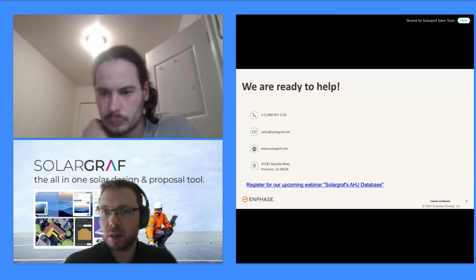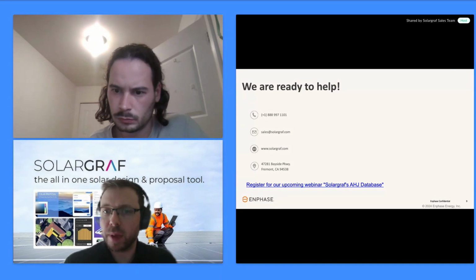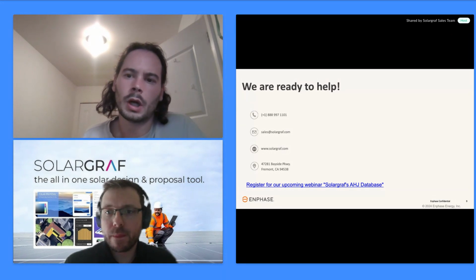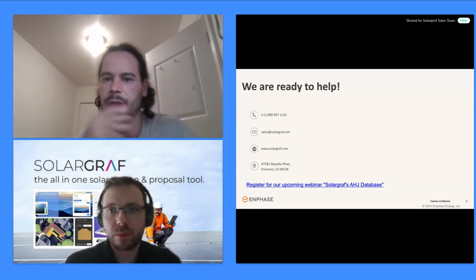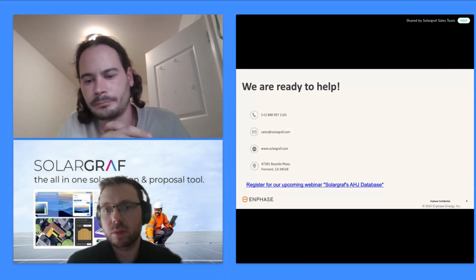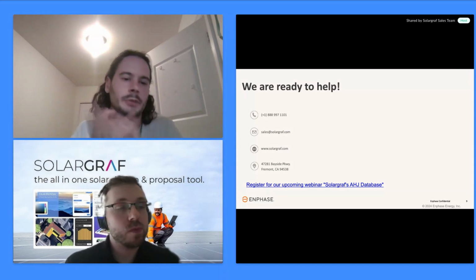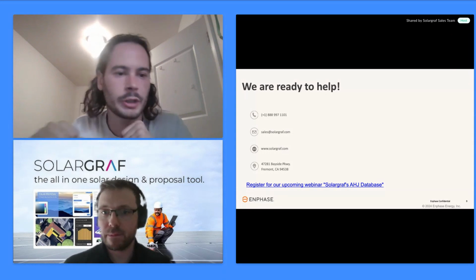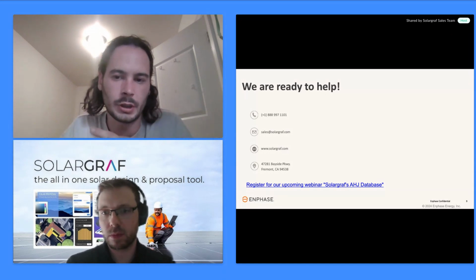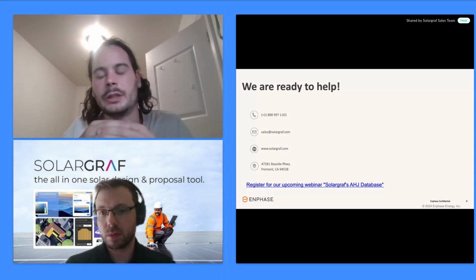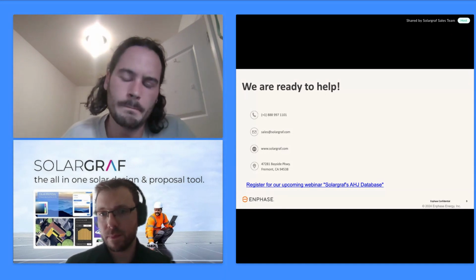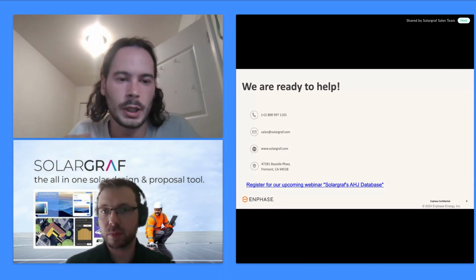Another one from Isaac here. Looking to know more about the PSA using new panels versus old panel settings. Oh, yeah. I think that's probably PCS. Yeah, definitely. So essentially, Isaac, one of the problems that we've heard from installers, especially in the US, is that the PV system that's being designed has quite a large current that's pushing out, and the existing main panel cannot handle that current. So you're left with essentially a choice. Either you design a smaller system, which may not be ideal, because you want to be producing a large amount of energy throughout as long a time of the day as you can, or you can upgrade the main panel, but that's quite expensive.